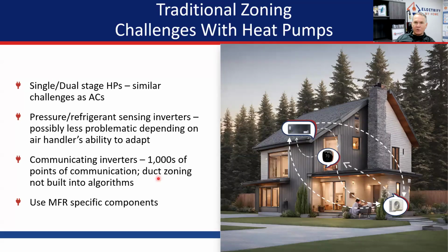Communicating inverters have thousands of points of communication in there. They will move in small increments based on the temperature inside, outside, and what the thermostat is telling it. So there's a communication algorithm going on in there. Those are not designed to have traditional zoning installed on them, because that traditional zoning is not communicating with the system, and the system starts to get all these weird false readings and unpredictable readings in the algorithm.